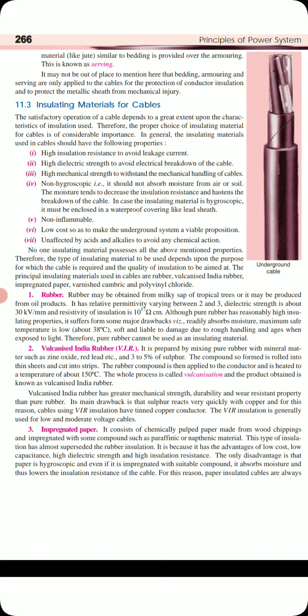It is prepared by mixing rubber with mineral matter such as zinc oxide, red lead, and 3 to 5% of sulfur. The compound so formed is rolled into thin sheets and cut into strips. The rubber compound is then applied to the conductor and heated to a temperature of about 150 degrees centigrade. The whole process is called vulcanization. So vulcanized rubber gives more strength over plain rubber.